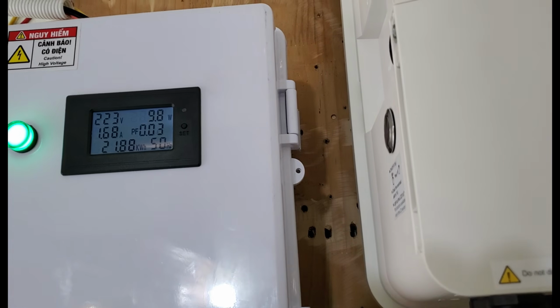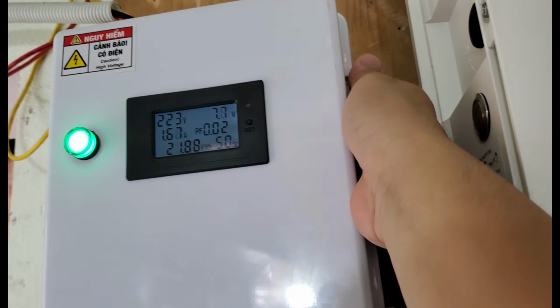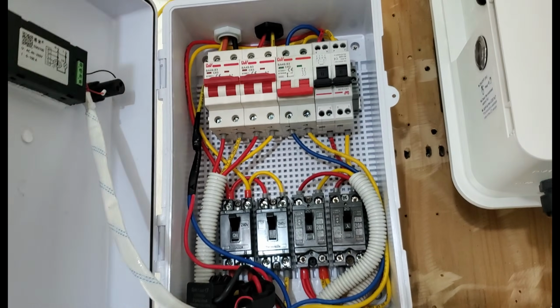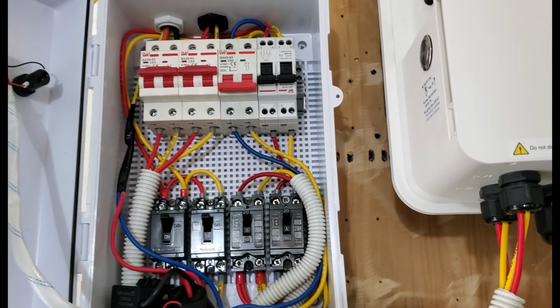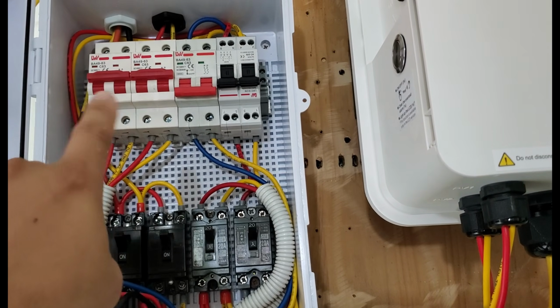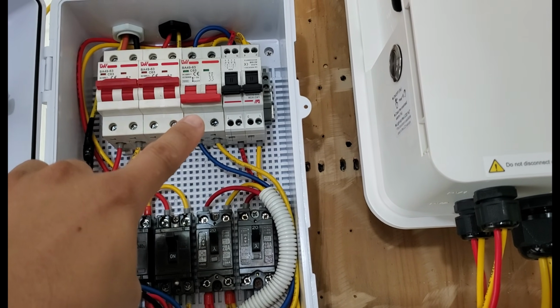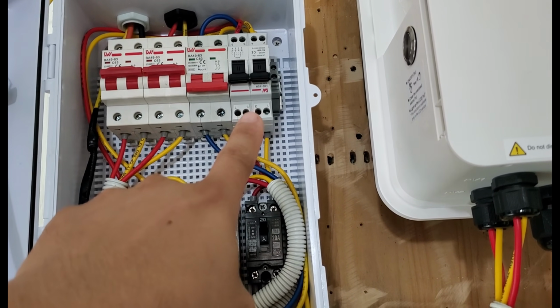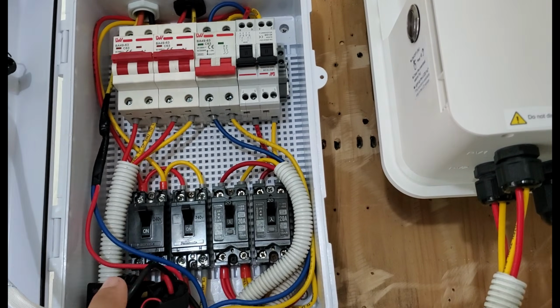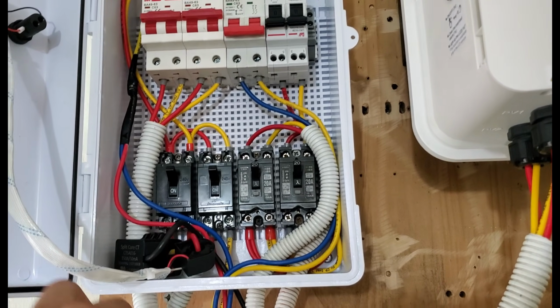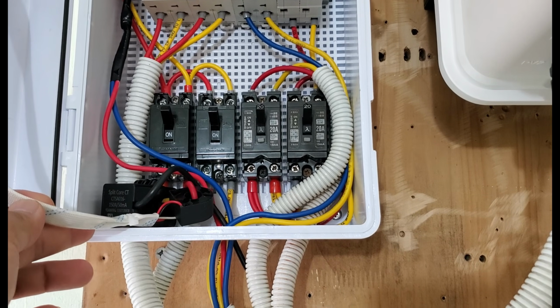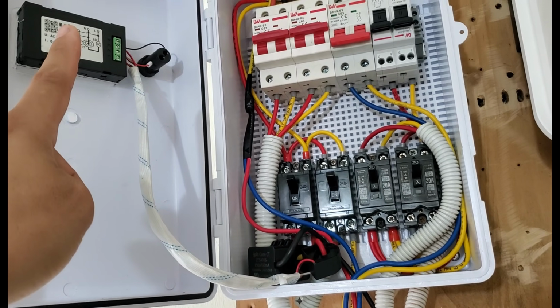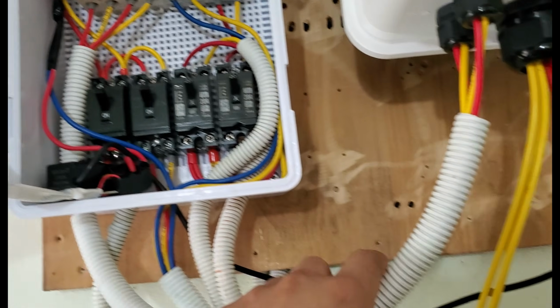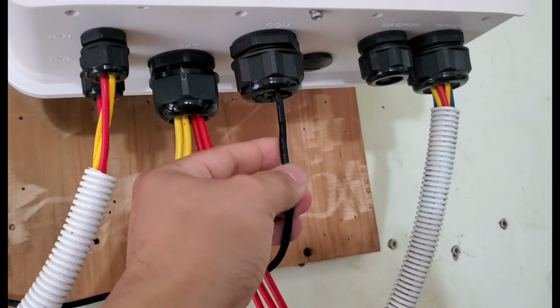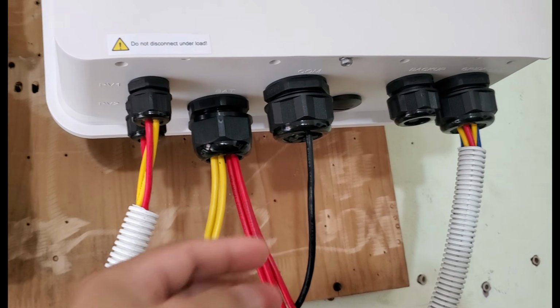Since I installed it myself for personal use, the setup isn't exactly the cleanest. Wiring's a bit messy. When I have some free time, I'll tidy everything up and make it more organized. I also added a small electrical cabinet to house the necessary breakers. There are two MCBs for the two PV strings and a transfer switch that allows the house to switch over to the backup output in case of a grid outage. There are also a few additional MCBs for different household circuits.